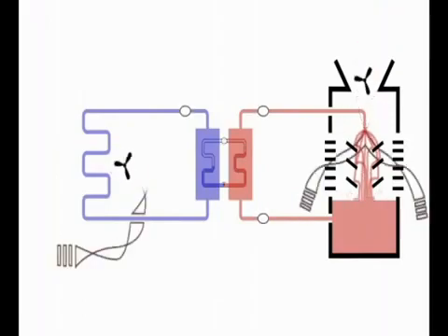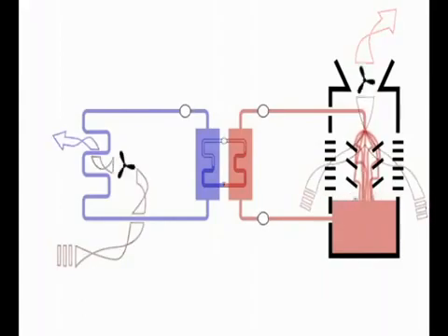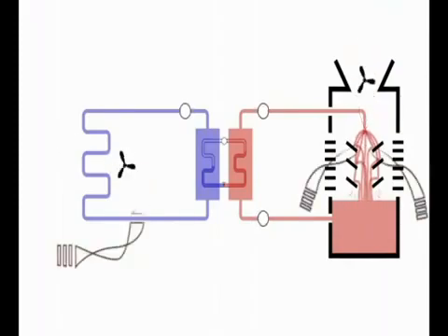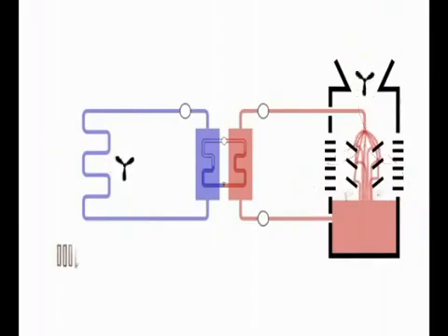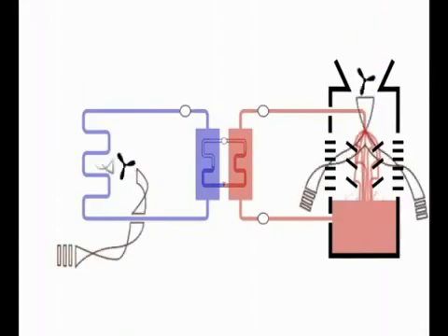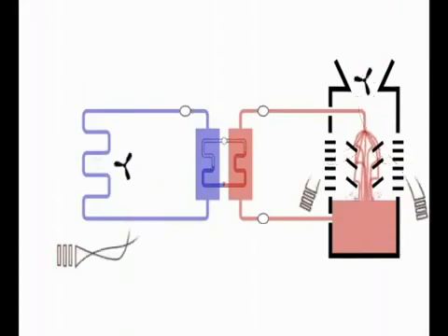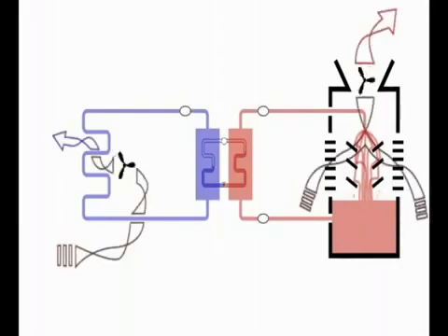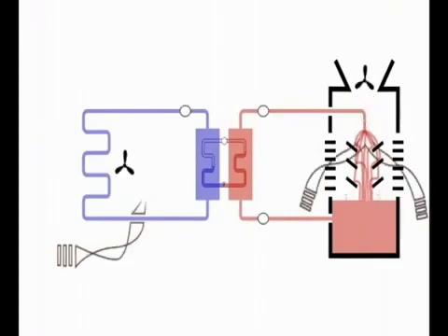This distribution network using water is complicated, but not exceptionally complex. Let's review. Water is cooled by the evaporator and distributed to the air handling units to cool room air. A separate loop of water cools the condenser and carries its heat to the outside air via a cooling tower. You've seen cooling towers on roofs and adjacent to buildings, or as part of central chiller plants. The machine that does the compression refrigeration loop in this layout is termed a chiller.